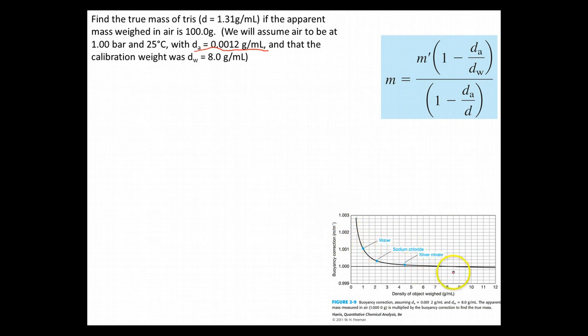So, now, you can see that if I'm using an 8-gram weight to calibrate it, there's going to be no correction needed when the object is 8 grams. Now, if the object is lighter than 8 grams, there's going to be some buoyancy. And so the object is going to basically be floating in air just a little bit more than the brass weight was. And so it's going to appear to be lighter than it actually is. So we have to use this correction factor to fix that.